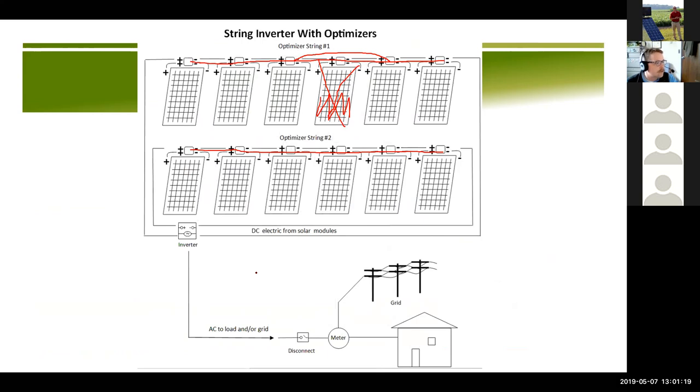There's another additional value, which is that if the power were to go out, I can actually cut the electricity off all the way to the solar panel level, which is a safety thing. So for roof mounted systems, this can work well because it fits the new electric code. The previous version we saw, if roof mounted, does not meet the new 2017 electric code without an additional piece of equipment. But ground mounted does meet the electric code. That's why I still present it, because if it's ground mounted, it does meet the electric code.